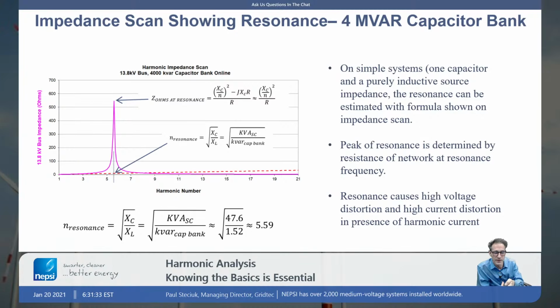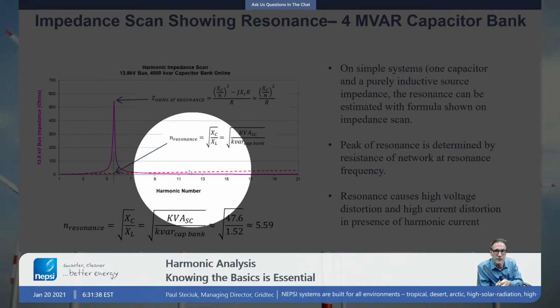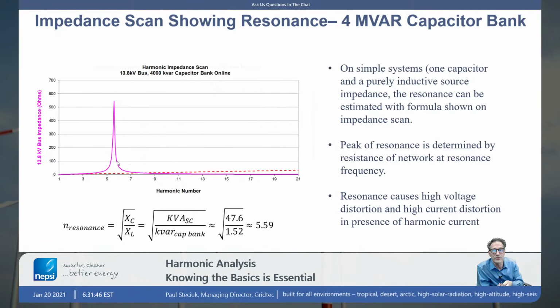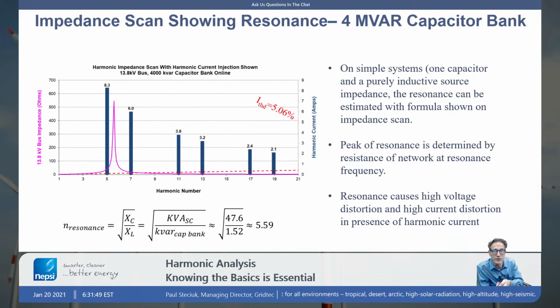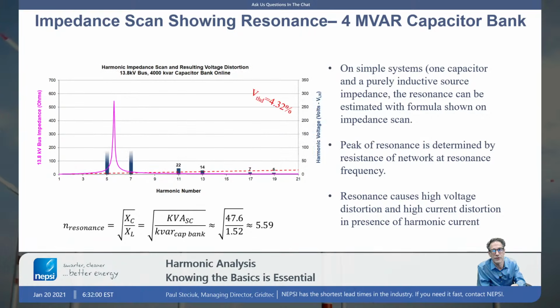What have we done? We have increased the impedance of this network at all harmonics basically less than the 9th harmonic here. You can see we're greater than, which means that if we had current injection, we're multiplying that value of current times more impedance at each and every harmonic number, resulting in more voltage distortion, and that's what we show here. The voltage distortion now is 4.32%. So it's just marginally acceptable. We would consider 5% our value of acceptance.